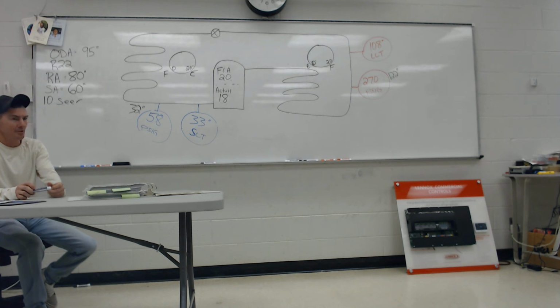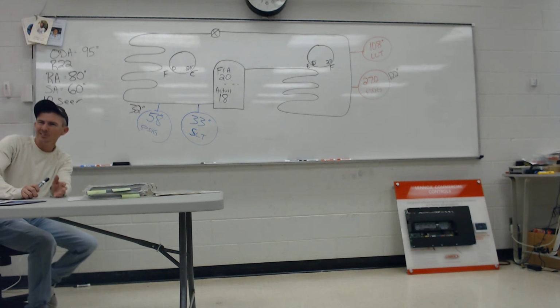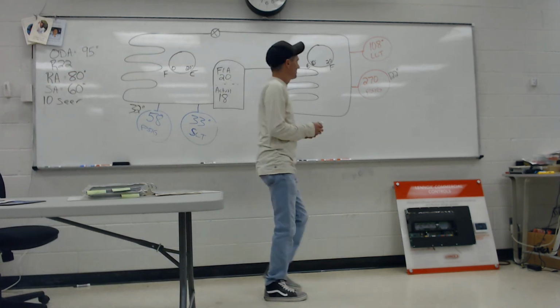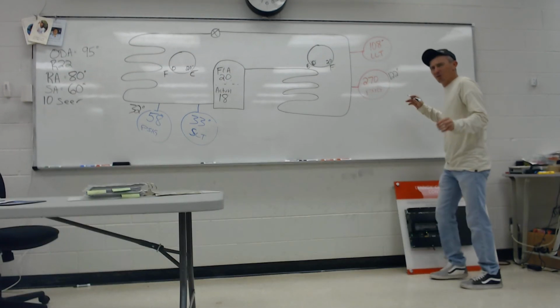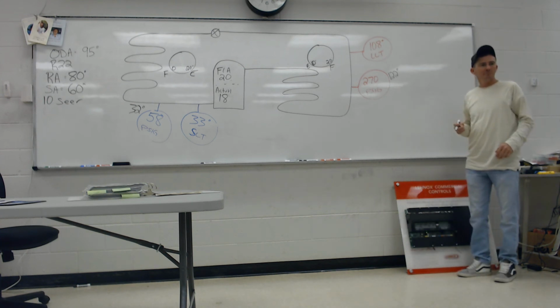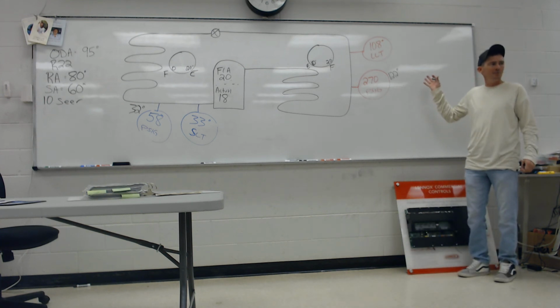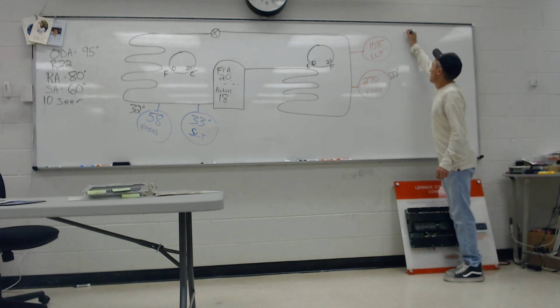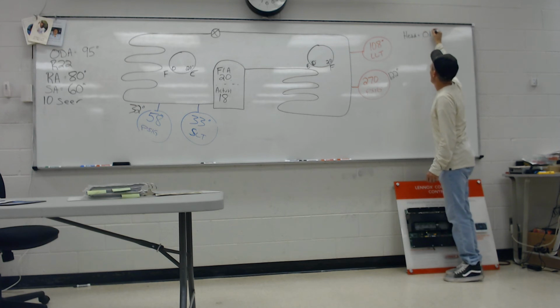How's my condenser look, guys? A lot of subcooling. At 108 to 122, it's like 14 degrees of subcooling. It's got a little bit of extra subcooling, right? That's good. It's good to be a little bit flooded. Still not a huge red flag, but I'd store it in the back of my head. So my head pressure is okay.